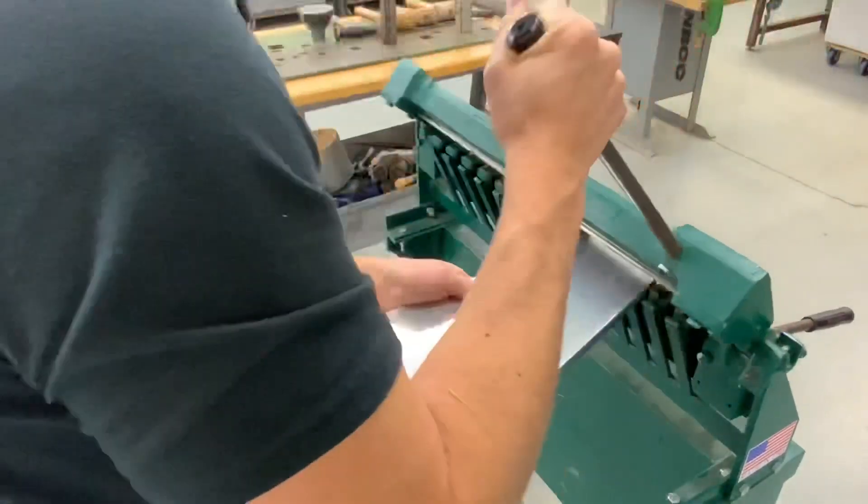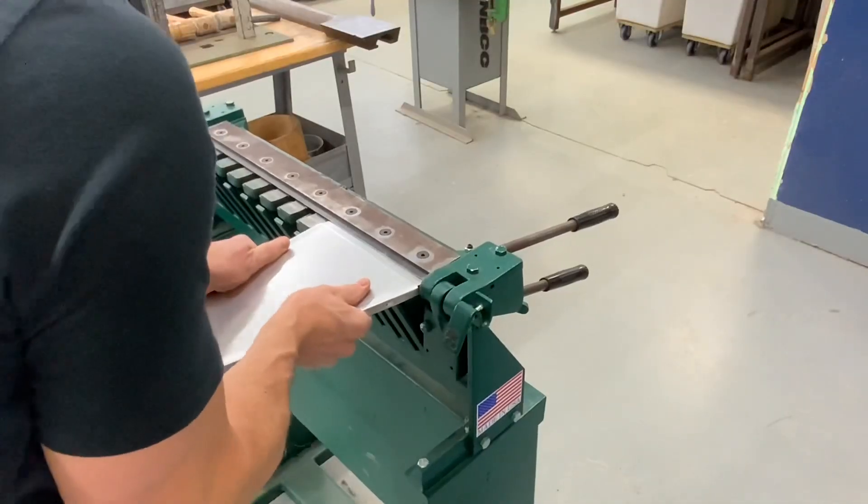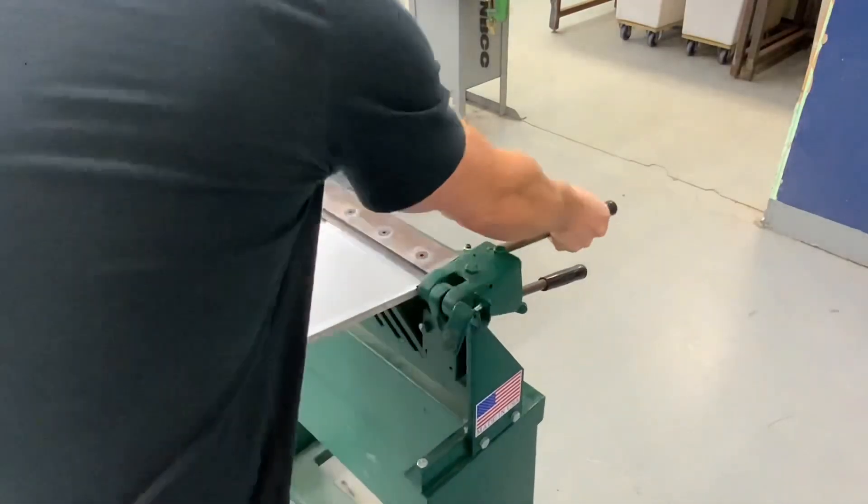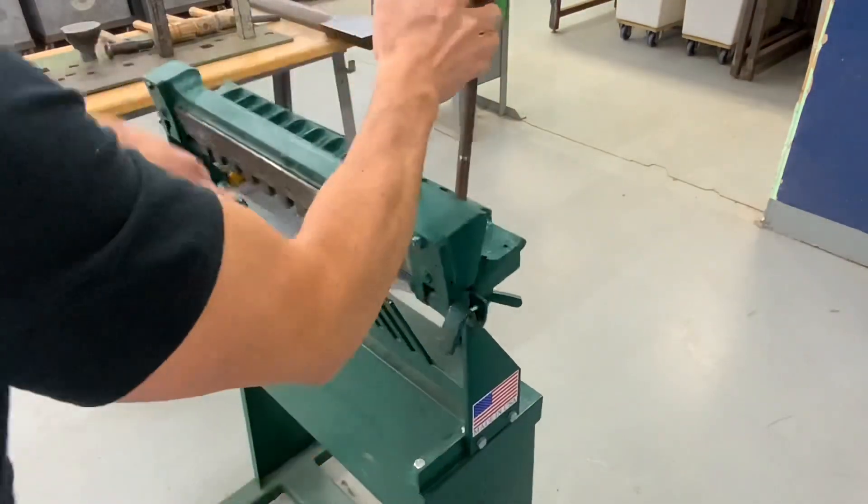Now that that is done, I will bend my drive cleats. And in most cases, don't forget, the drive cleats go on the short side of the duct.